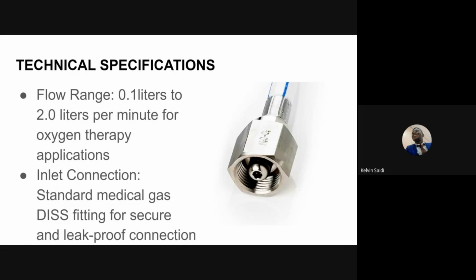When we are talking about the inlet connection, the inlet connection of an oxygen splitter commonly features a standard medical gas DISS fitting, and this guarantees a secure and leak-proof connection with the oxygen source. The image to your right shows how a DISS fitting looks, and I'm sure most technicians on this call have come across this one.